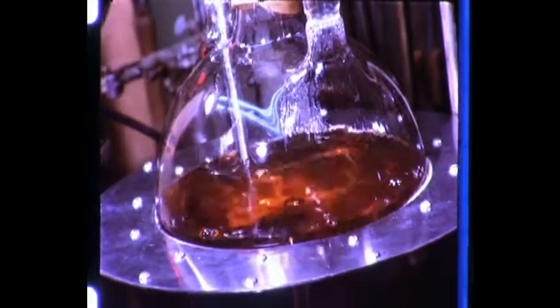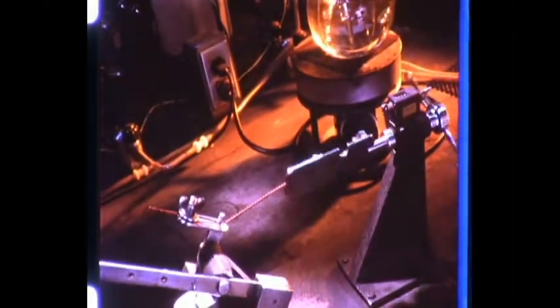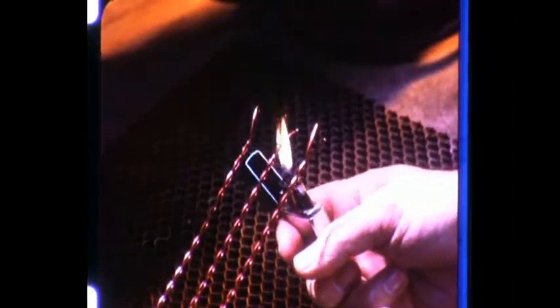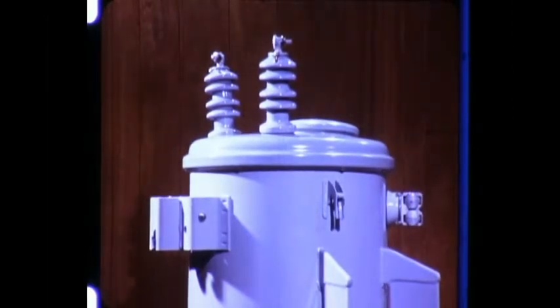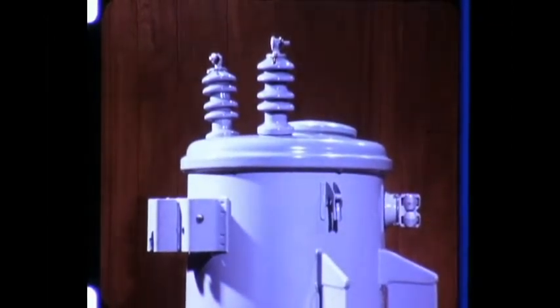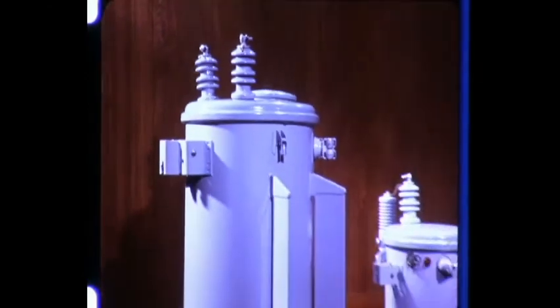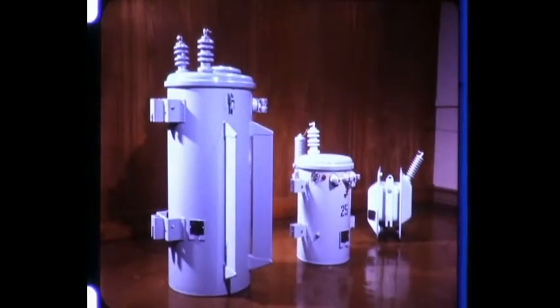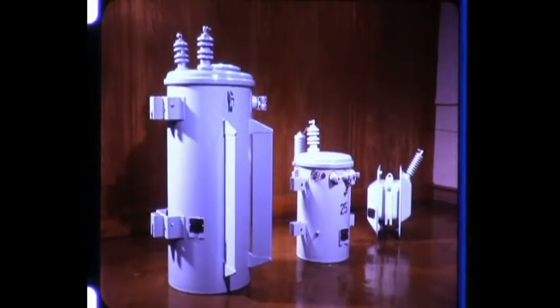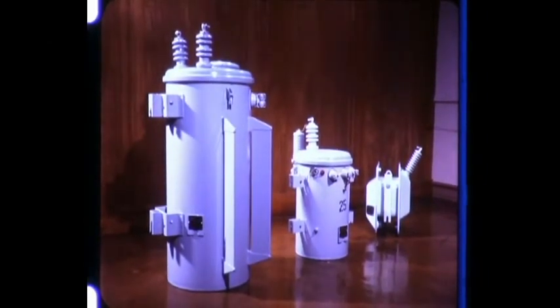Experiments on resins to develop a wire enamel with superior strength and temperature characteristics. The result? A stronger, tougher new enamel with 50% greater voltage breakdown strength, withstands 30 degrees centigrade more heat. G-Mel. Tailoring the molecule in paper and wire enamel has enabled GE to reduce the weight since 1959 of 25 kVA transformers from 495 pounds to 282 pounds in the new seal-pack transformer.